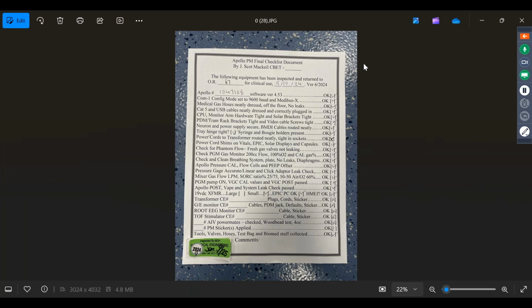So moving on, they have a test called the post-test, VGC post-test, that tests the ventilator performance. And at that point, you're done. Then you go into the other stuff, making sure you have a good transformer for the Epic PC, making sure the Epic PC is okay, because it's not part of the anesthesia machine PM, but if the Epic PC is not happy, the doctors aren't happy.